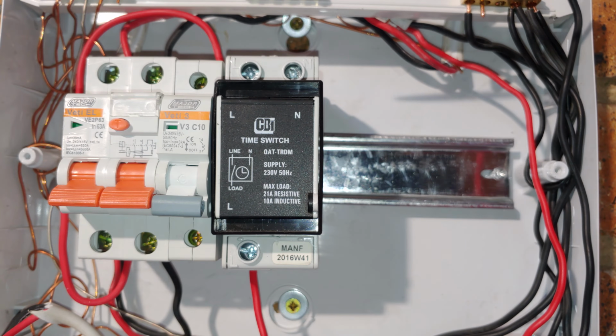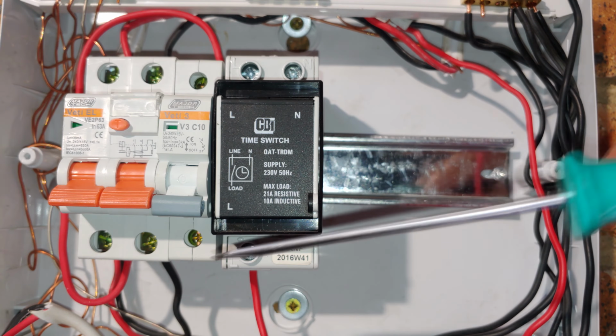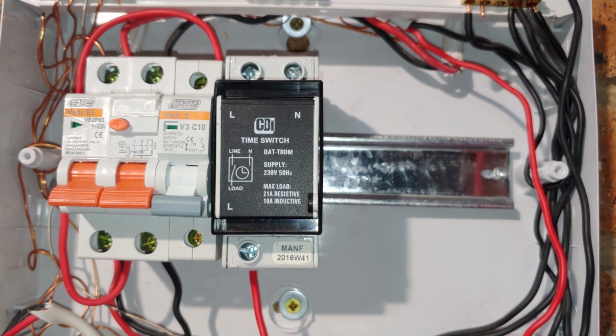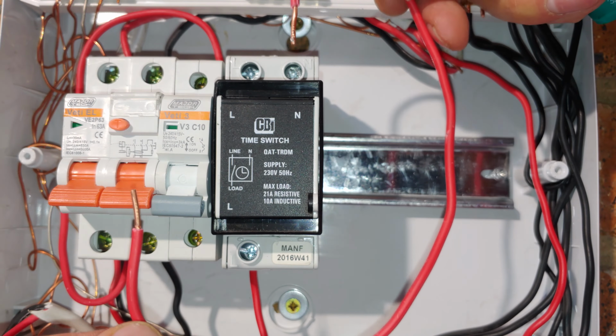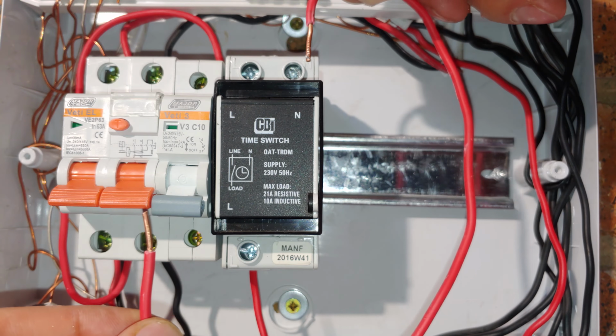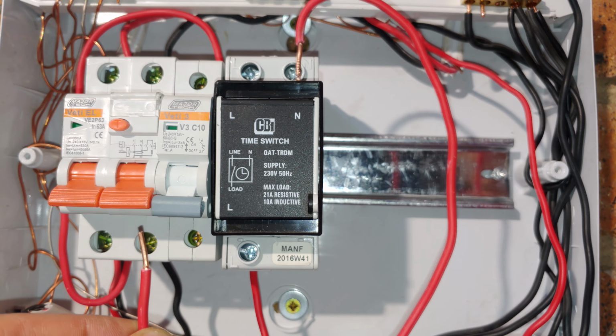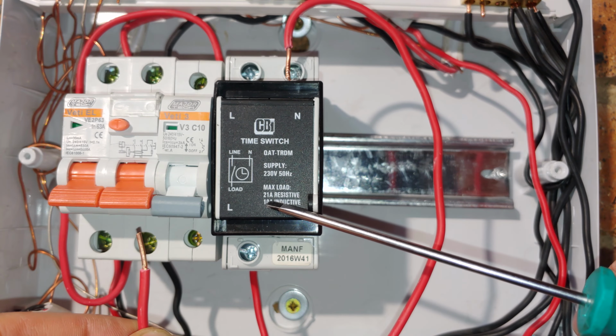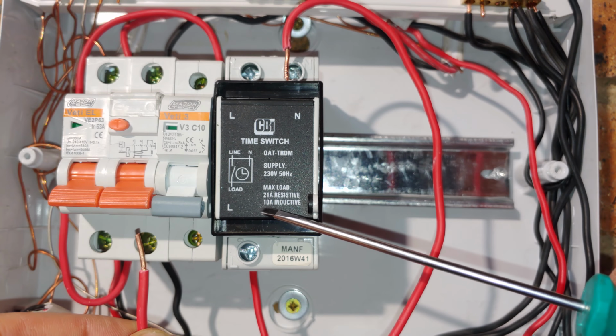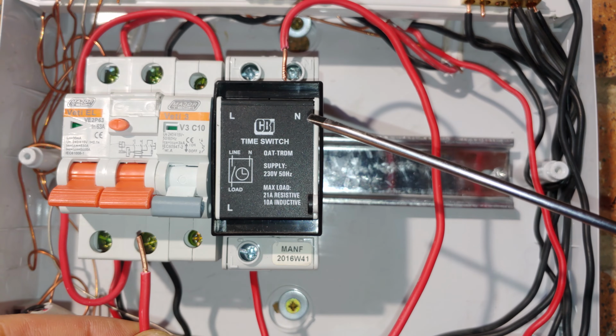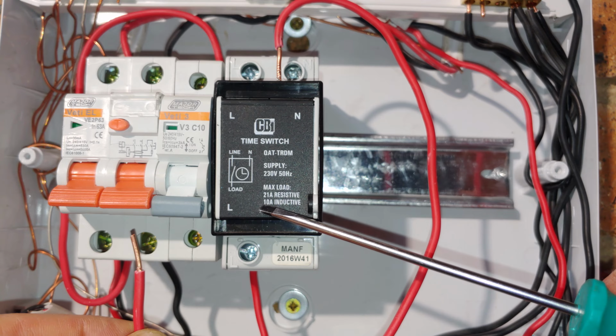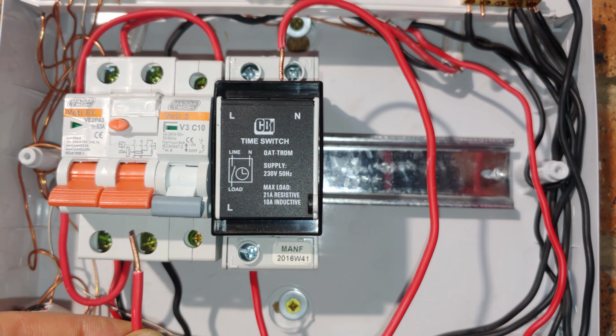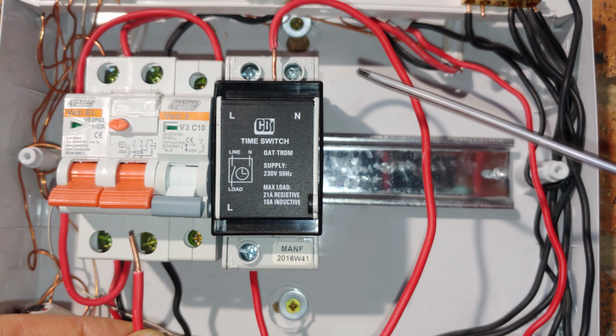Now this timer switch only requires another live and a neutral, but this particular live is very important. It must come from the output of the circuit breaker. So that means you'll have to have a wire that looks something like this. Now the size of the wire is very important. This happens to be a 21 amp circuit breaker, meaning it can carry a current carrying capacity of a maximum of 21 amps. You will need to match the wire to the load.